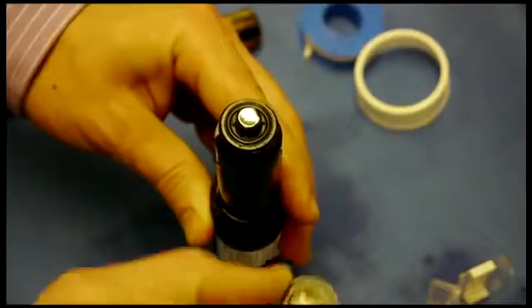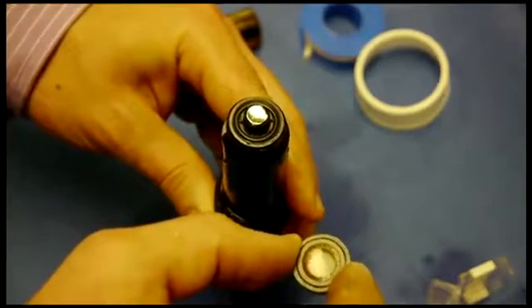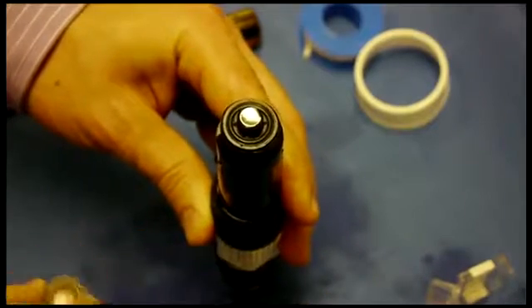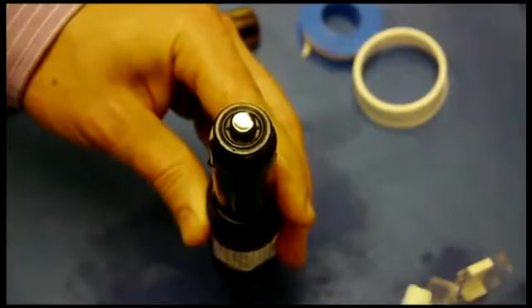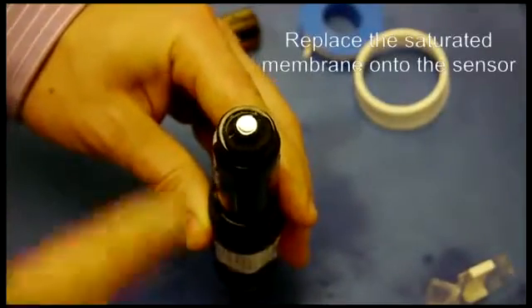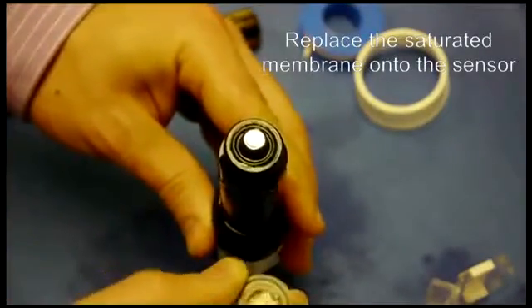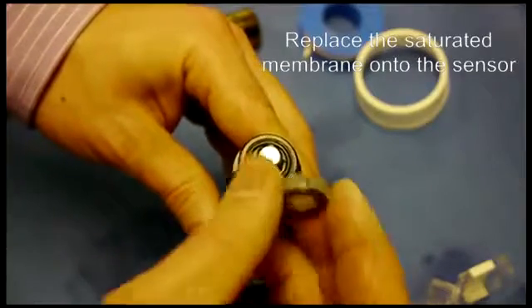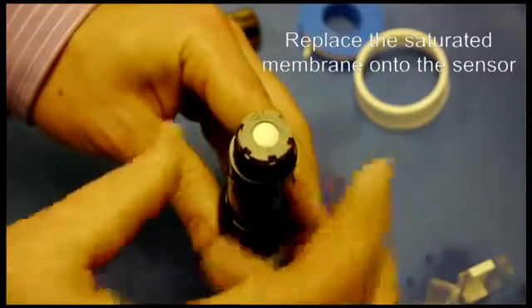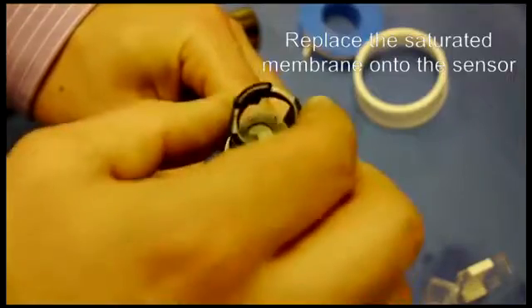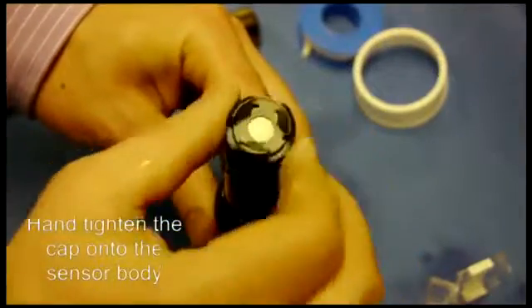Next grab the membrane assembly which I've been letting soak this whole time. Get the electrolyte solution and pour it over the cathode and make sure it's completely drenched and saturated. Then take the membrane assembly, place it on top, and then get the membrane retainer and screw it on snug.